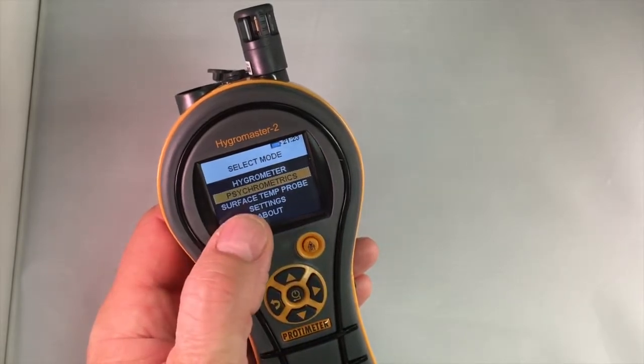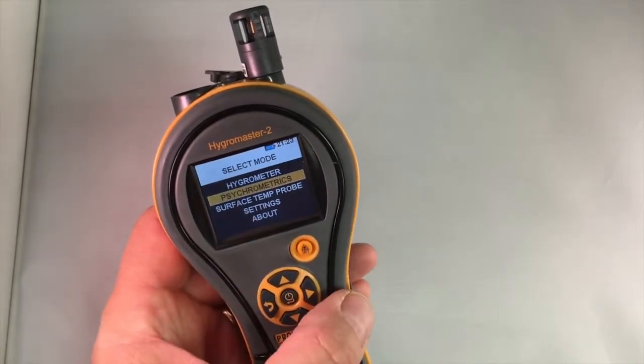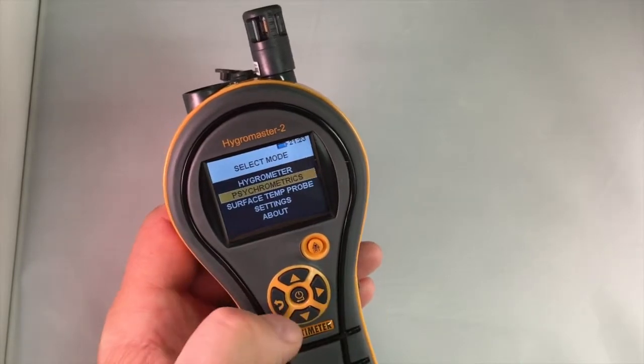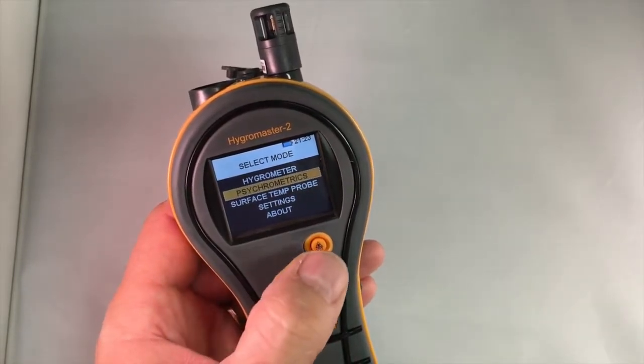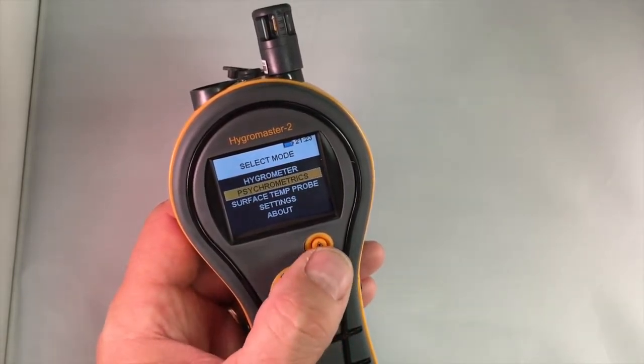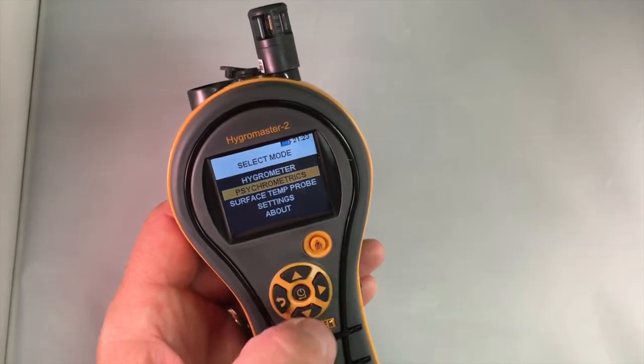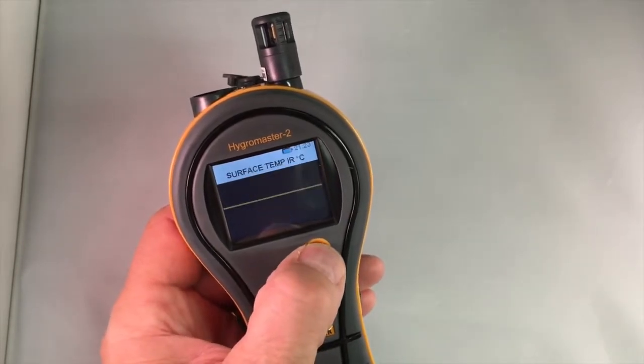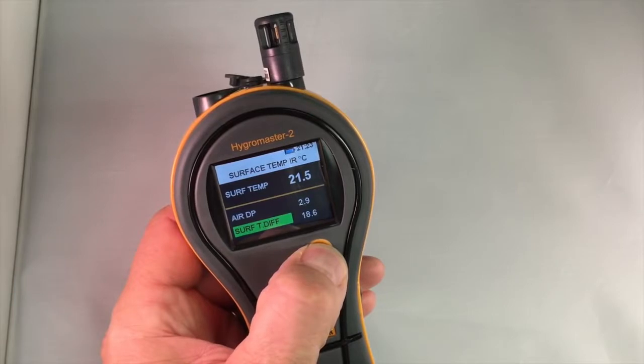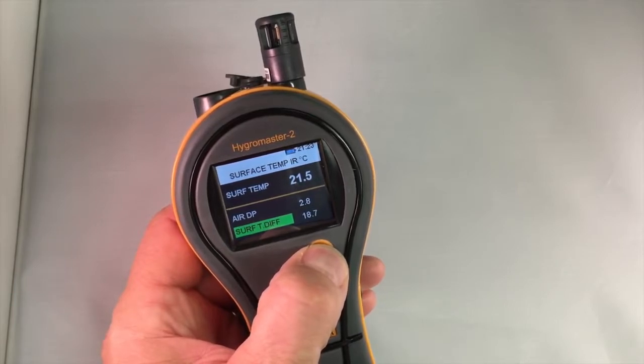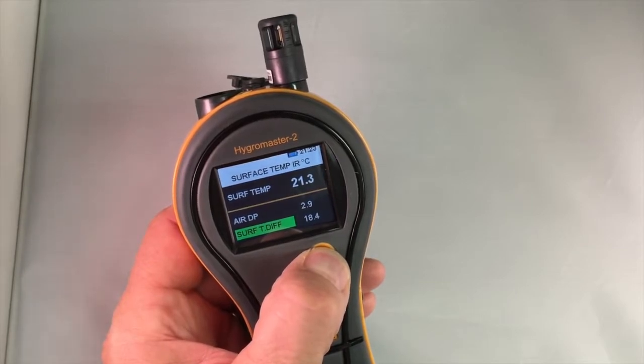You'll notice it says surface temperature probe. Actually, that's for an auxiliary surface temperature probe that you can plug into the side for certain applications. But we also have an infrared surface temperature sensor with laser pointer, and you just start that by pushing this button here. You'll see immediately the surface temperature at the top, the dew point, and our surface temperature differential, meaning the surface's proximity to dew point.